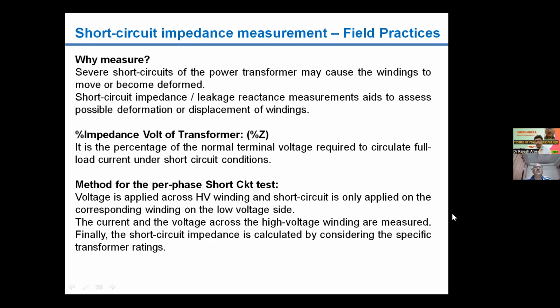It is also done to measure the leakage reactance of the transformer, which is nothing but an indication of the voltage regulation, a design parameter of the transformer, showing how much voltage regulation will take place. Generally in BSES our transformers have a percentage impedance of nearly 13 to 14%, and accordingly the voltage regulation will take place. What is voltage regulation? It is the drop in the terminal voltage of the transformer when you load it from no load to full load. So for that reason also, to check whether the design parameter is okay or not, we do this test.